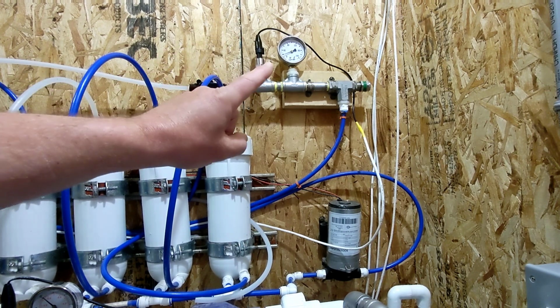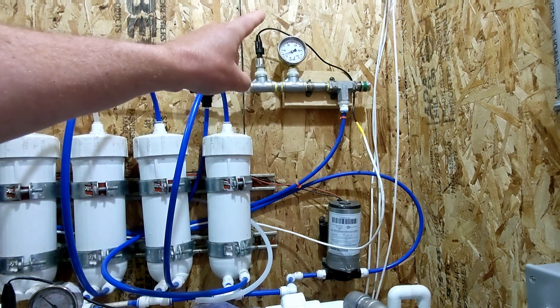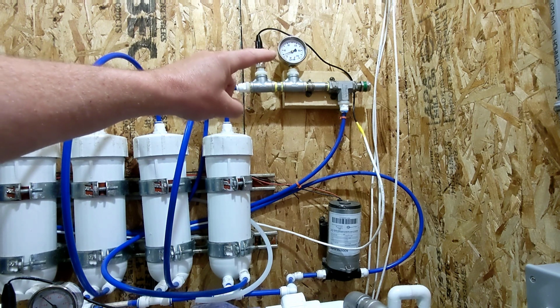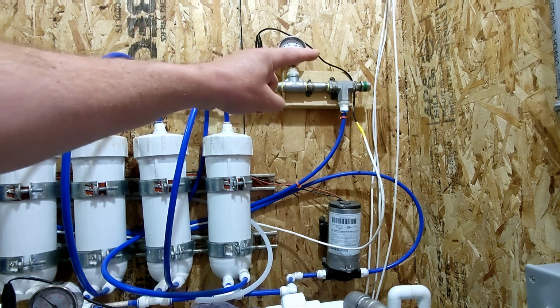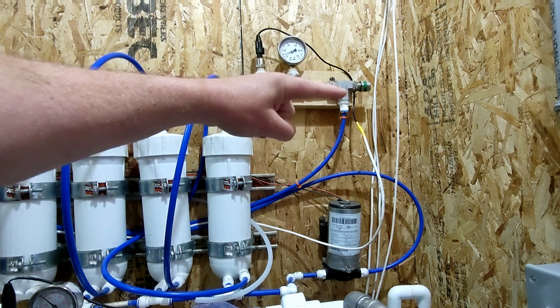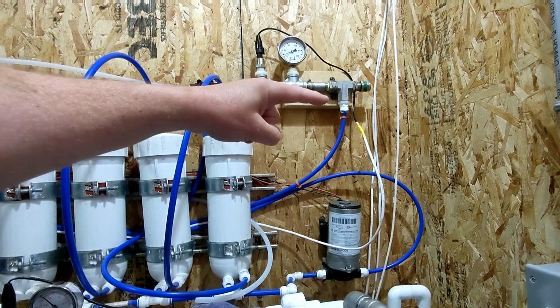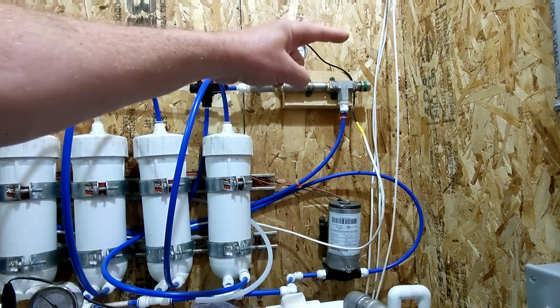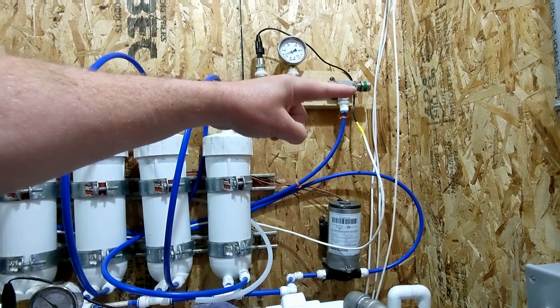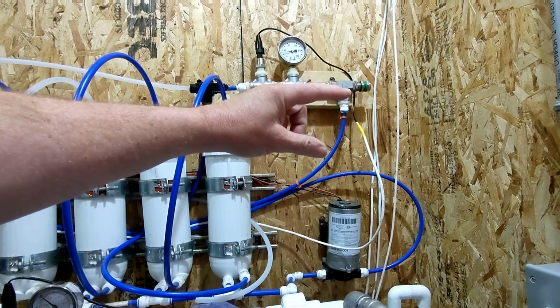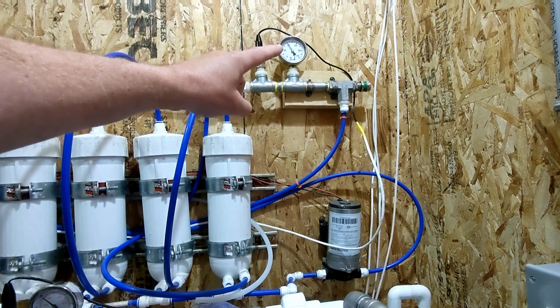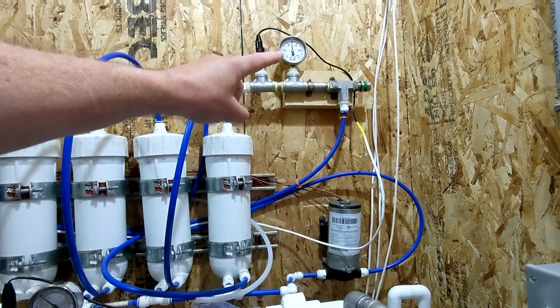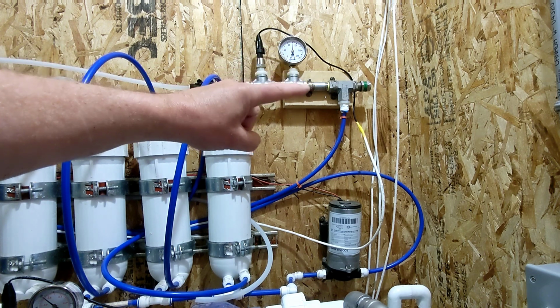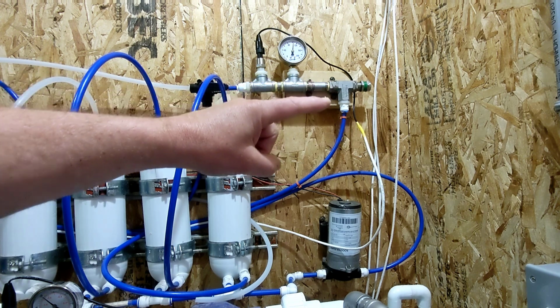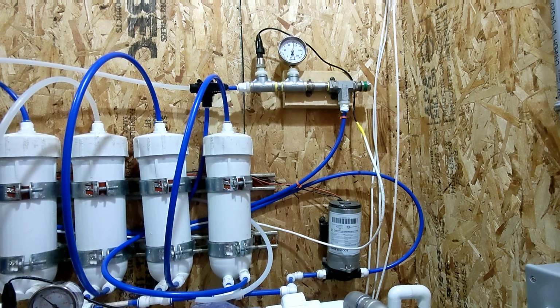Then next to the pressure transducer is a pressure gauge, and we could have looked at that and seen that it was 12.5 just by reading the gauge. And then the next thing up is a Hycalock pressure relief valve. And what that does is that lets me adjust this green knob on the end. And what that does, oh, here, the RO's just come on. So you see the pressure going up? And what that Hycalock valve does is it lets me dial in that pressure. So we'll wait until the system gets up to pressure here, and then I'll mess with it.